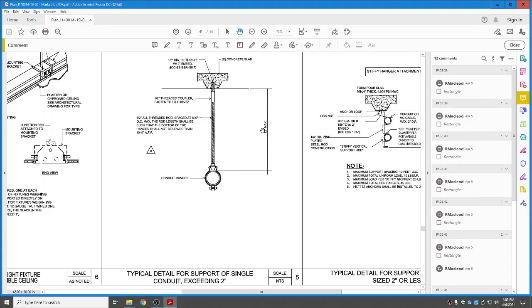So the architect is intentionally giving these details to suggest that there aren't some issues relating to some seismic bracing that might be required. Because if it's 12 inches or less, we don't have to seismically brace. And there are certain exceptions to that that would be in your seismic bracing manual.